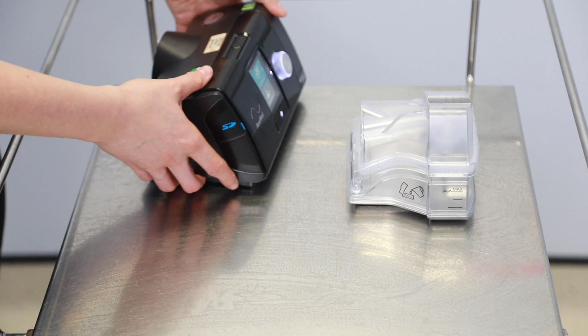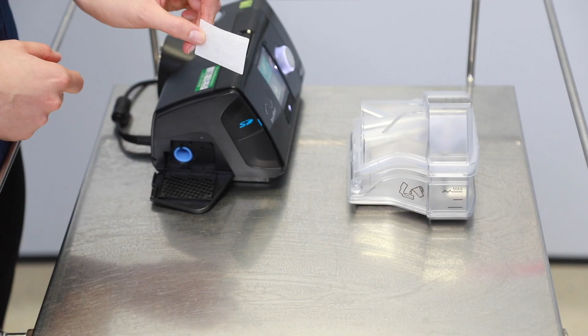Your machine is essentially like a compressor and therefore uses room air. This air passes through a filter located at the side of the machine. Use the catch at the back of the machine to access the filter. Every few days you should take the filter out and flick it to remove the dust. Every 6 months, or if the filter appears dirty, replace it with a new one. Spare filters have been provided.